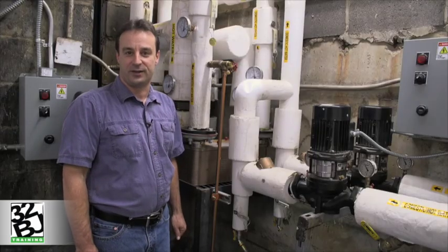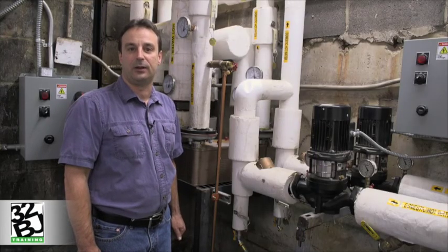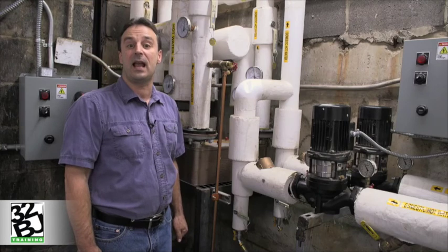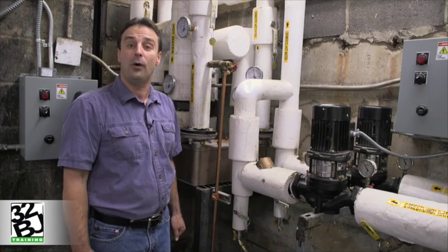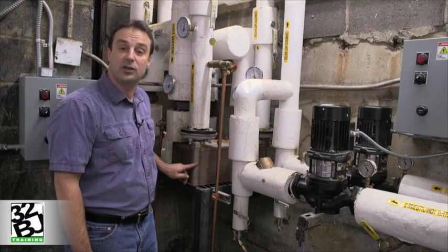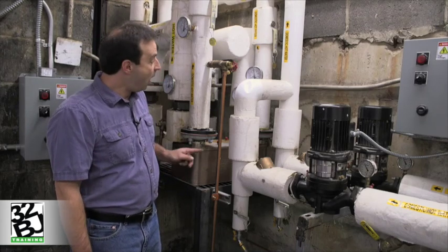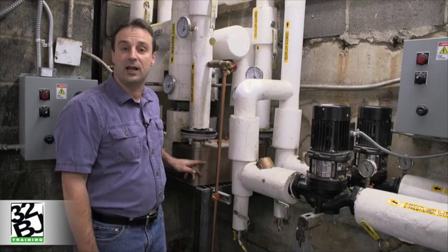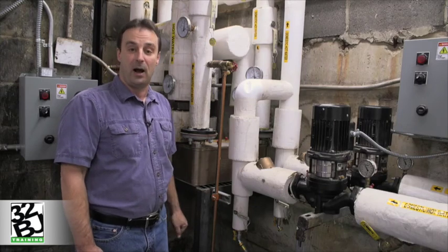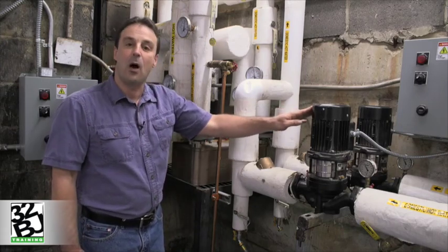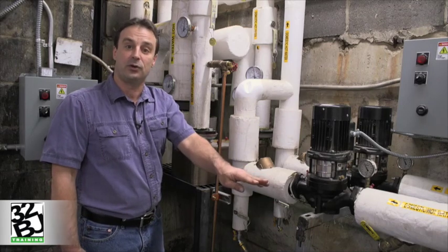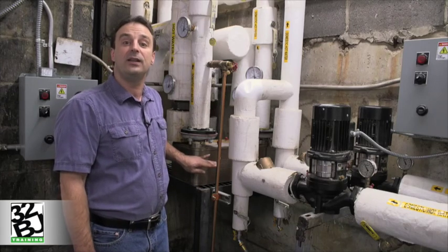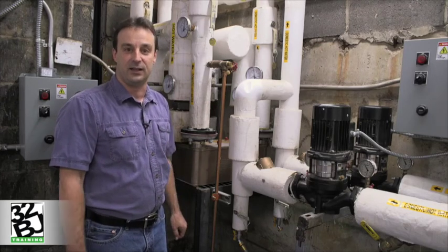Another type of domestic hot water system that may be encountered in large-scale multifamily residential buildings is a type of indirect system. This system uses a hydronic or steam boiler to produce hot water or steam that is sent over to a small plate frame heat exchanger. On the other side of that plate frame heat exchanger, cooled domestic water is passed through the heat exchanger to be heated for hot water use by the residents. Small domestic hot water pumps take the cooler water from the storage tanks, pump it through the plate frame heat exchanger to absorb the heat and be raised to 120 degrees Fahrenheit for the residents to use.